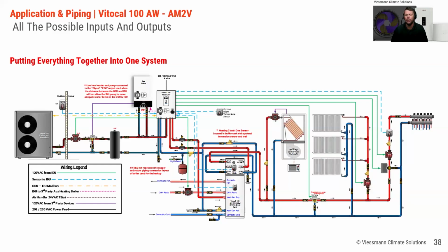There's a lot of variables in that. But if you are using a tank that is on the open market, make sure it is a cooling buffer tank and not just a heating buffer tank. There's going to be a lot more insulation on the cooling buffer tank. Same thing with domestic hot water tanks. If you're going to choose somebody else's tank or it's already pre-existing, make sure it's good for low temperature applications. We're only supplying 140 degrees out of the refrigerant circuit alone. With that backup element heat, after a time delay, you can boost it up to about 160, 165.